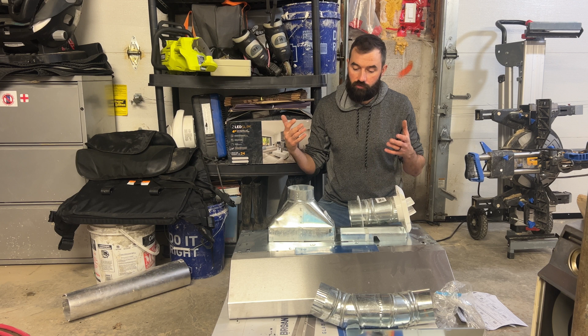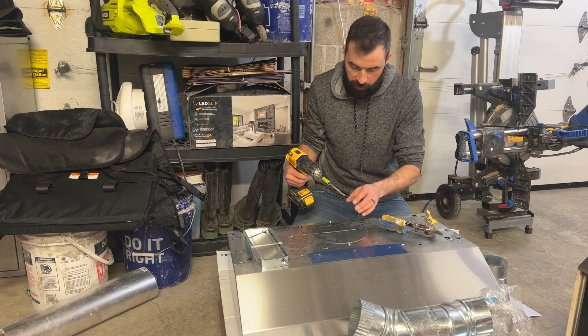The unit itself has a couple of different knockout areas. The sheet metal has prefabricated cutouts in it to match the venting application you choose. Like I said, there are a few different ways this can be set up. In my case, the knockout is right here. There's another one for a circular duct that could go right here, and then there's one at the back of the unit as well. So obviously choose the one that matches the way you're completing the vent work.